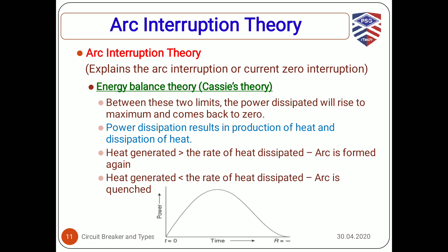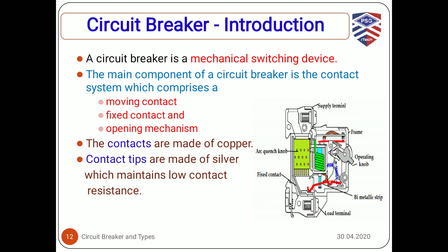Next, let's move on to circuit breakers and the introductory fundamental concepts of circuit breakers. So circuit breakers are mechanical switching devices. They consist of various components. The major components of the circuit breaker are the contact system, which consists of moving contact, fixed contact, and the opening mechanism. The fixed and moving contacts are made of copper, and the tips of the contacts are made from silver, because we need to have low contact resistance.